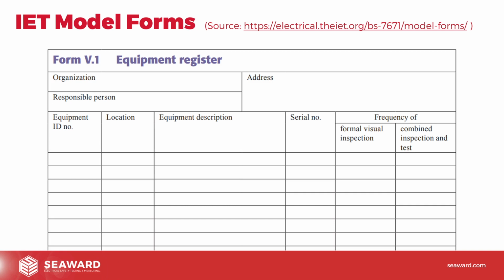You need to uniquely identify each piece of equipment, and then that number should accompany that piece of equipment throughout its working life. So you issue it with a number at the start and use the same number all the way through. The reason we use the same number all the way through is for traceability. Maintenance records kept throughout the working life of the equipment, the traceability, any trends, patterns, repairs, any of that sort of thing we can track.